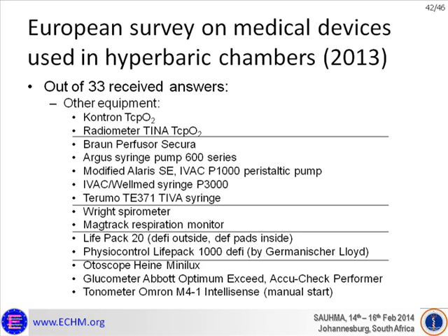However, one center is using also LifePack 20 as a defibrillator, just putting the device outside the chamber, and pads are installed on the patient inside the hyperbaric chamber, and other glucometers, tonometers or otoscopes which are entered inside the hyperbaric chamber.